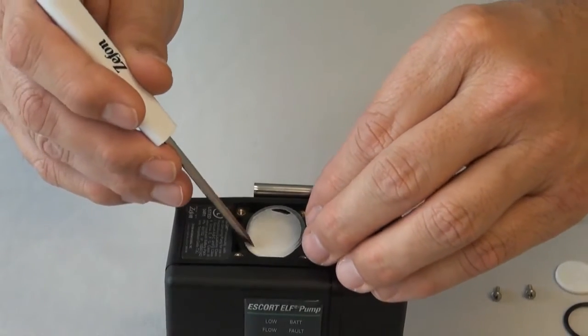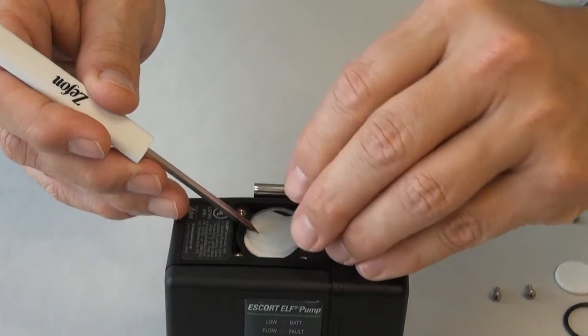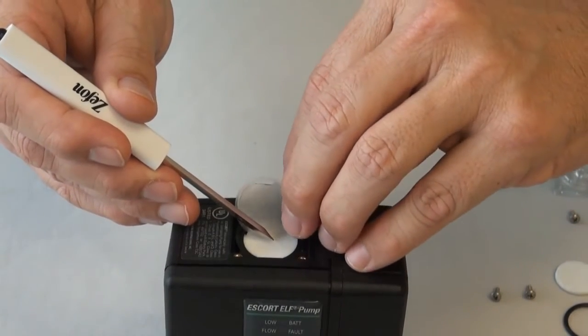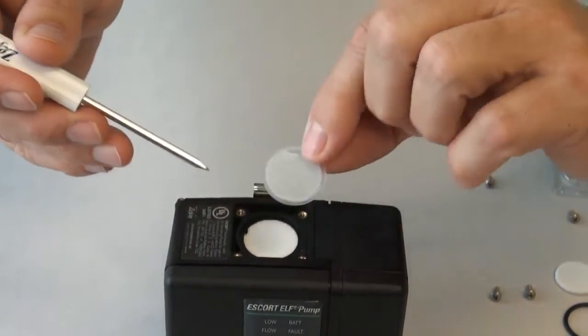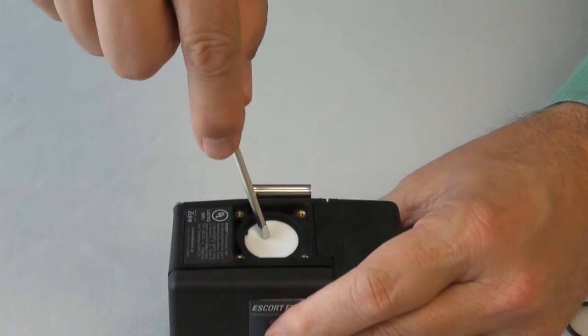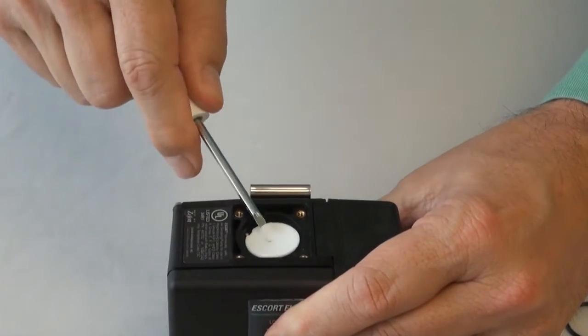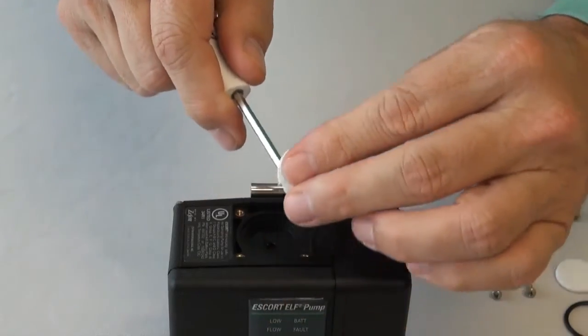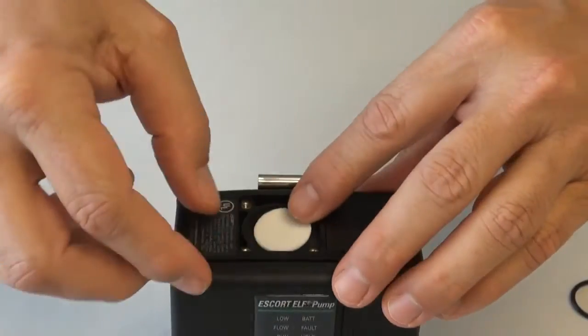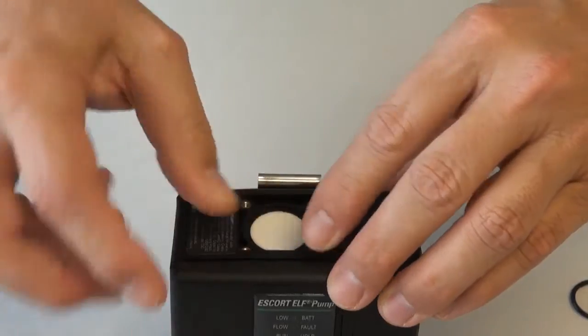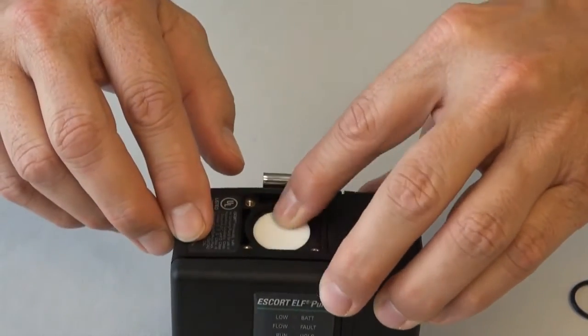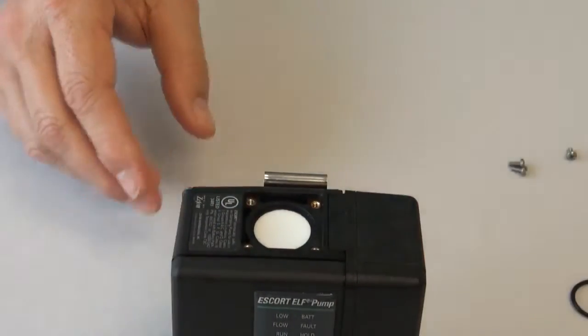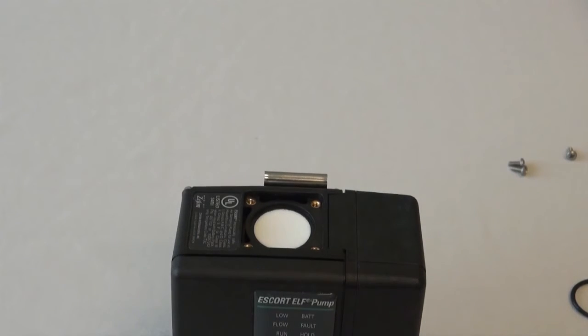If you are using the optional Teflon water stop filter, it should be removed and visually inspected for holes or other damage. Be very careful when removing and assembling, as it is very fragile and must be handled with care. To remove the filter frit, stab the center of the frit with a small screwdriver and lift out. To reassemble, place the rough side of the frit down and press into position. The filter frit should never need to be replaced if the other filters are properly maintained.